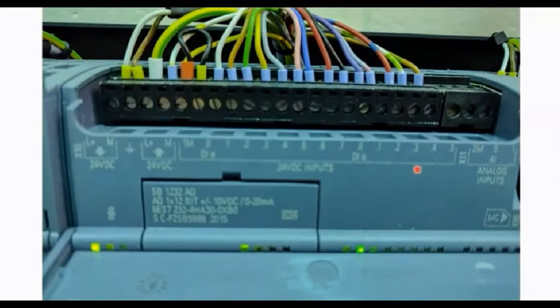So this DI B means its sink source is different. For example, the first 8 you can use with one sink, and then the next 6 you can use for a different sink. Maybe for the first you use positive syncing, and for the next you require negative, so you can connect here; DI B is the negative one. So you also have this option, which was not available previously.